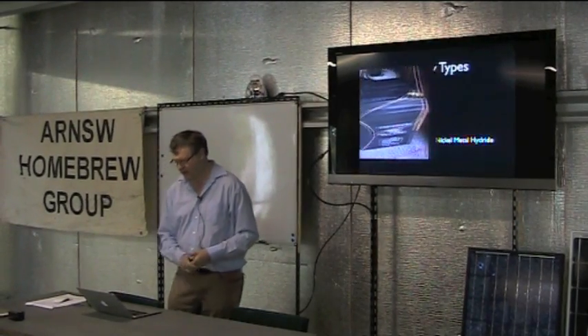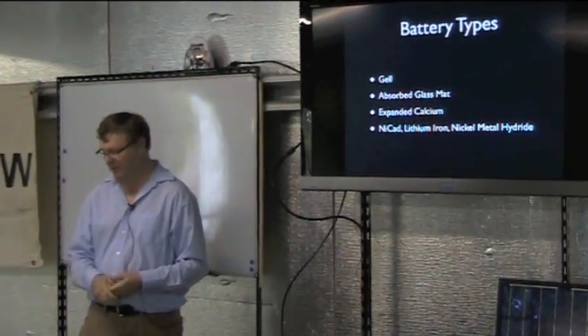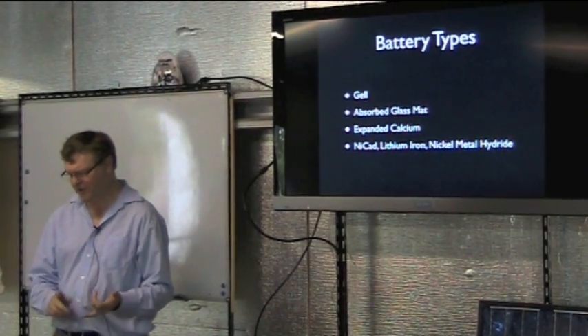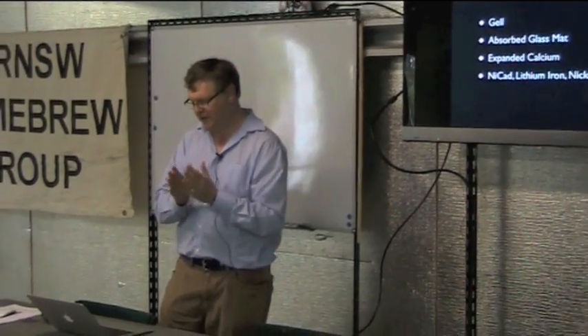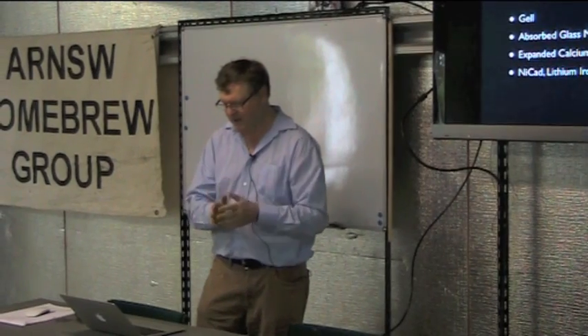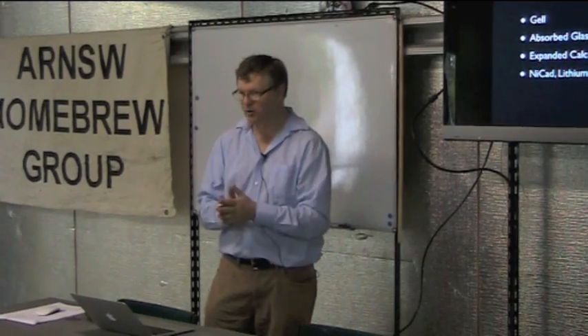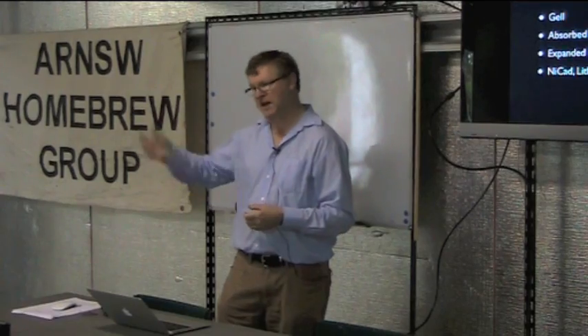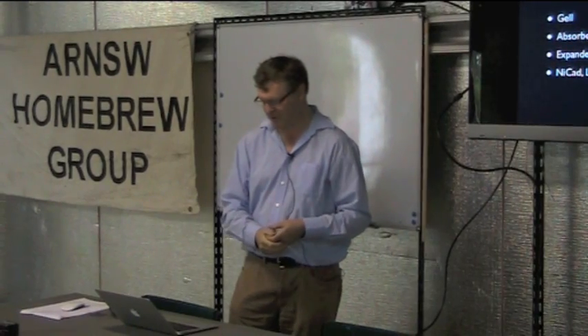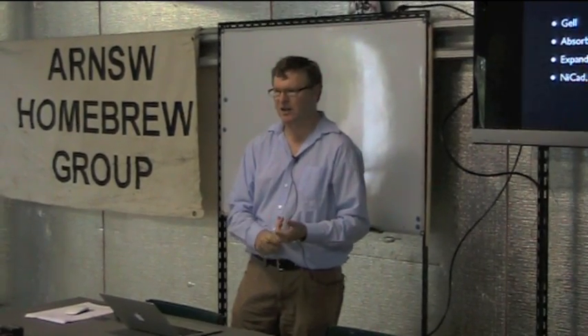Other types include gel cells — the electrolyte is in a jelly and they can operate in any position, are very stable, but have a higher internal resistance. There's also absorbed glass mat (AGM), which has a glass mat sandwiched between the electrodes holding the electrolyte by capillary action. A benefit of AGM is that if there is any gassing, the gas stays in place and can actually be reabsorbed. If you overcharge a valve regulated lead acid battery, that gas is lost, the electrolyte is lost, and you've damaged the battery. Calcium added to the electrodes reduces gassing and extends life.